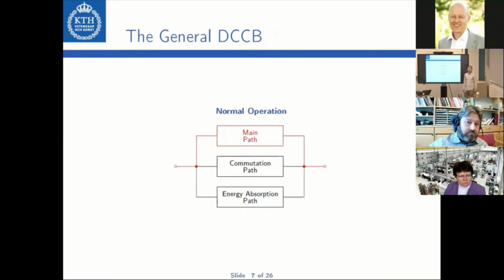In normal operation, the main path conducts. It should have a very low impedance and hence very low losses. If the DC circuit breaker is tripped, the current is commutated from the main path to the commutation path. Depending on the implementation, the delay of this stage will vary. After some time, the current is then commutated from the commutation path to the energy absorption path. The energy absorption path is responsible for inserting a counter voltage that drives the fault current to zero. This interrupts the current flow. The energy absorption path is typically implemented with metal oxide varistors, MOVs.